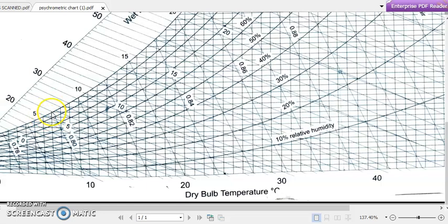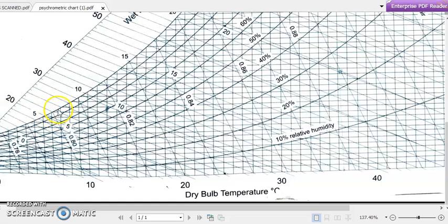Where the horizontal line meets the saturation line gives the corresponding dew point temperature — approximately 6 degrees Celsius. Between the markings of 5 and 10 degrees Celsius on the saturation line, there are 5 spacings, so we can read about 1 degree Celsius each. So the dew point temperature for air at 30 degrees Celsius dry bulb and 20 percent relative humidity is about 6 degrees Celsius.